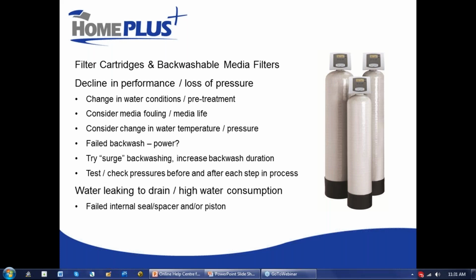But one of the most common signs of a problem or the start of a failure of one of those components is that water will leak to drain when you're in normal service mode. So if you hear water trickling to your drain, that's a very common issue, and you should service your seal and spacers and piston. Not a bad idea to have those parts on hand so that you don't experience any downtime, especially if you have older systems where parts may be more time consuming to obtain.